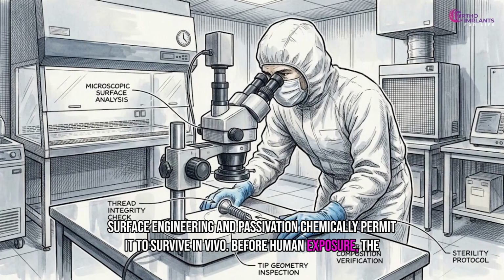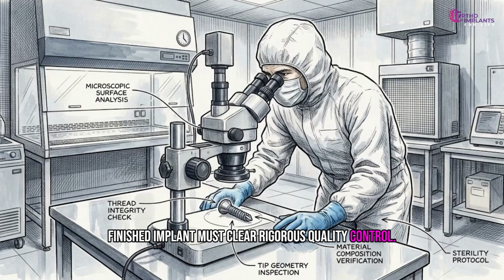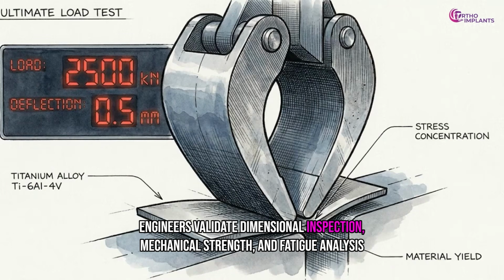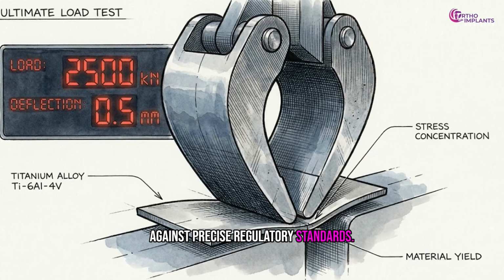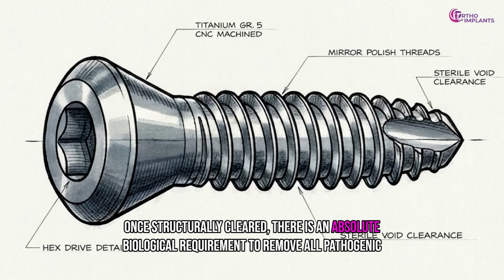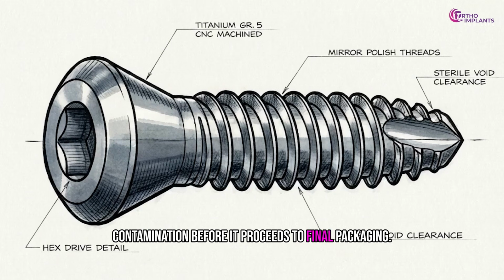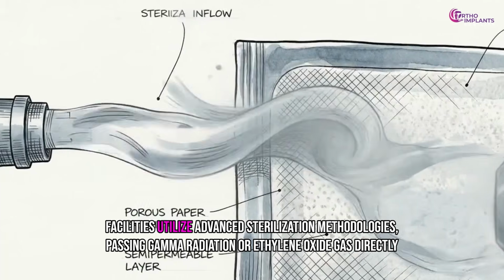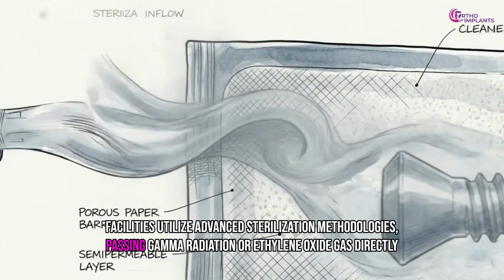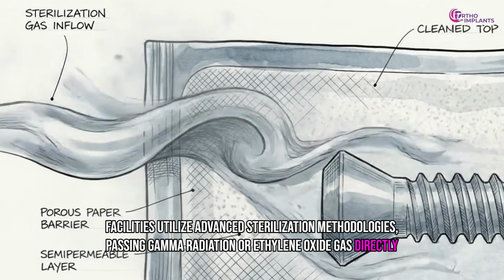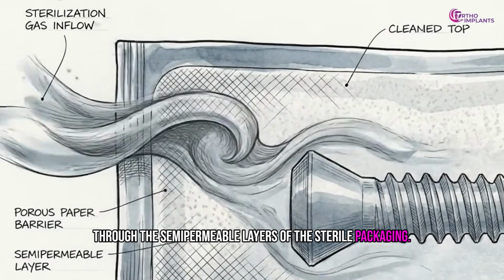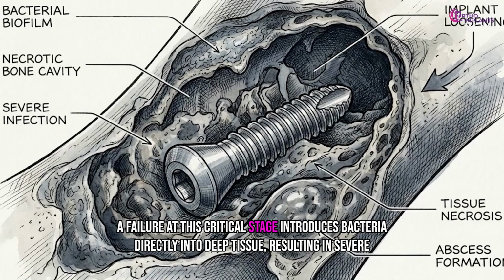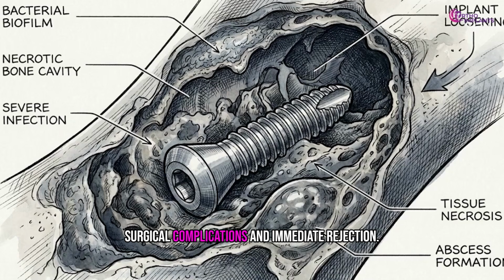Before human exposure, the finished implant must clear rigorous quality control. Engineers validate dimensional inspection, mechanical strength, and fatigue analysis against precise regulatory standards. Once structurally cleared, there is an absolute biological requirement to remove all pathogenic contamination before it proceeds to final packaging. Facilities utilize advanced sterilization methodologies, passing gamma radiation or ethylene oxide gas directly through the semi-permeable layers of the sterile packaging. A failure at this critical stage introduces bacteria directly into deep tissue, resulting in severe surgical complications and immediate rejection.